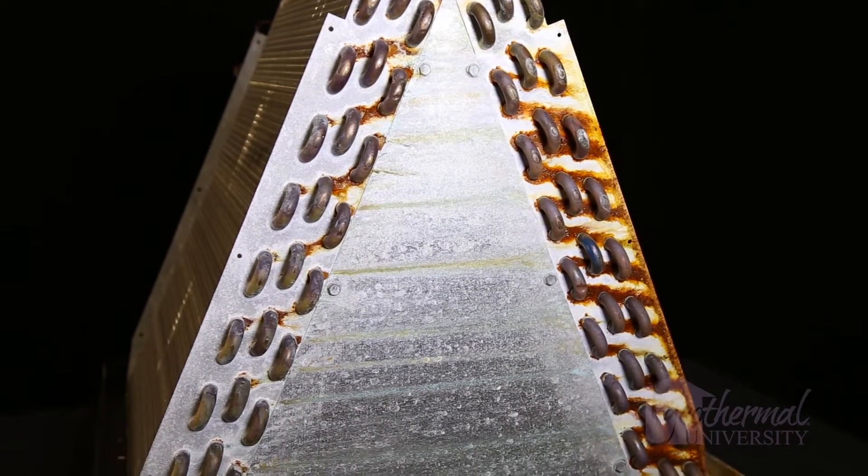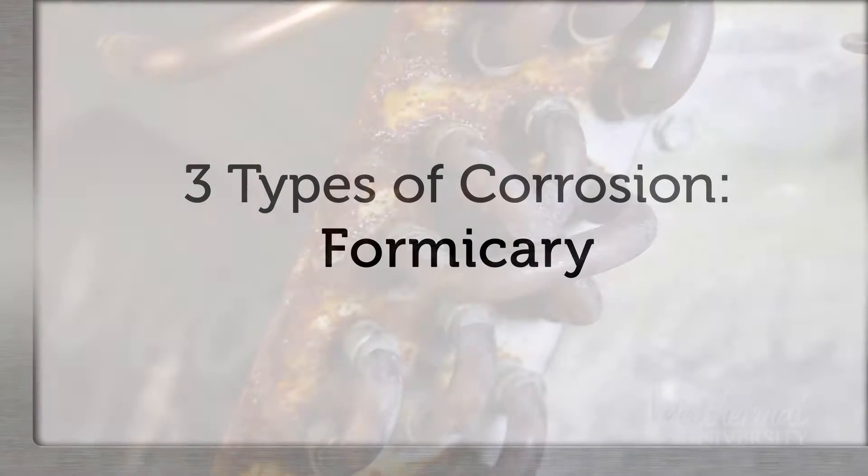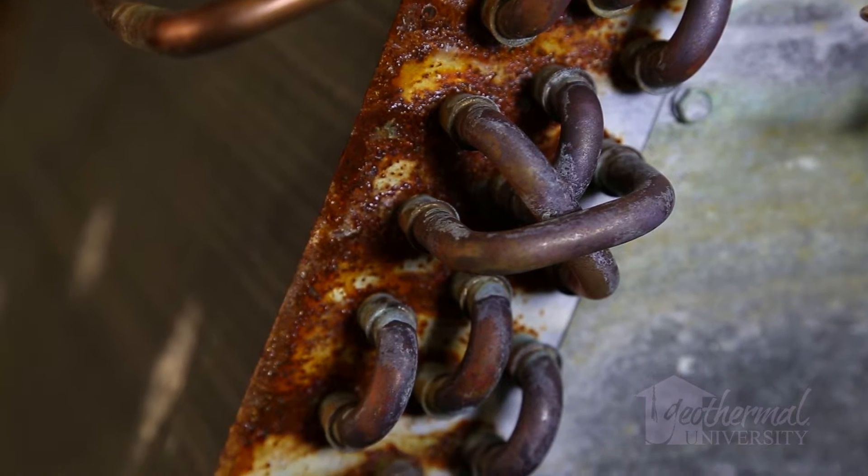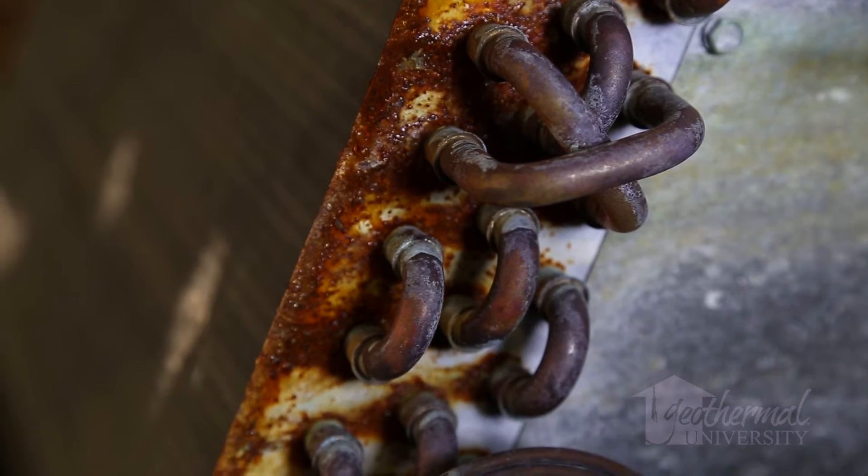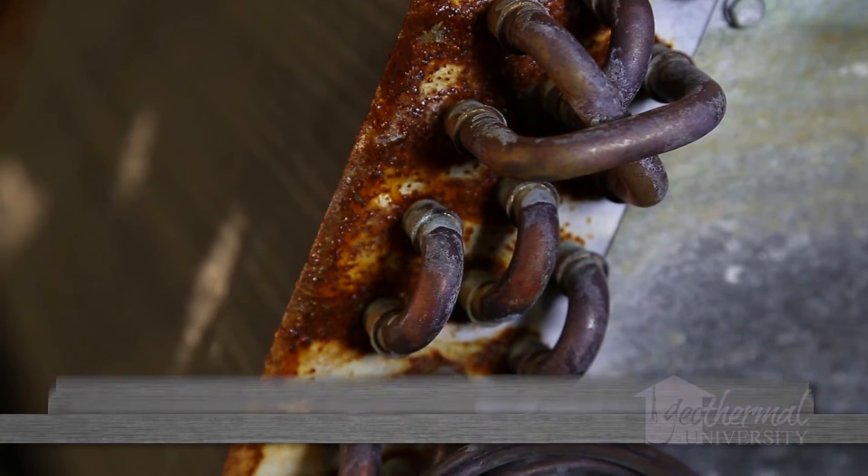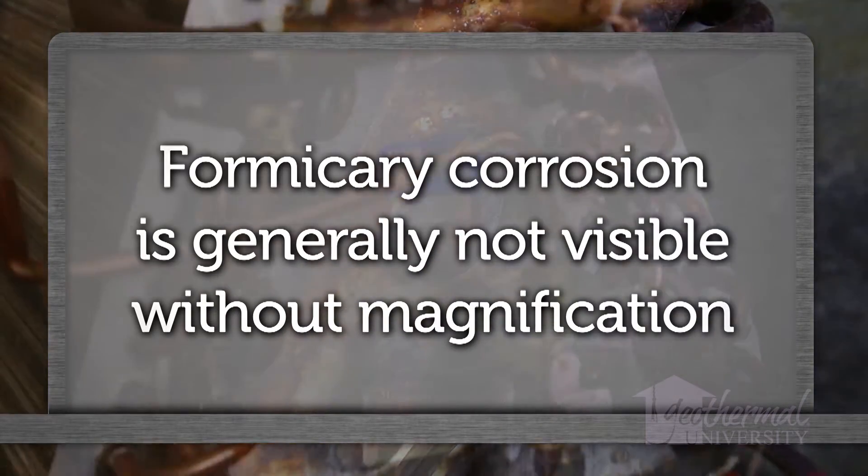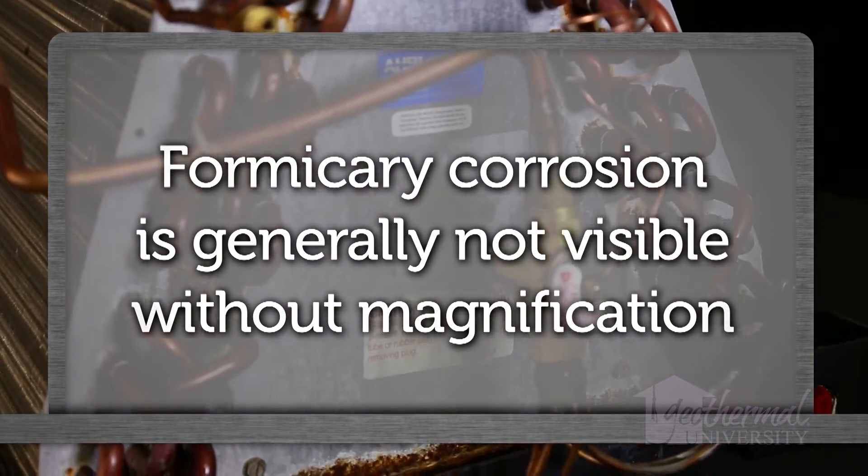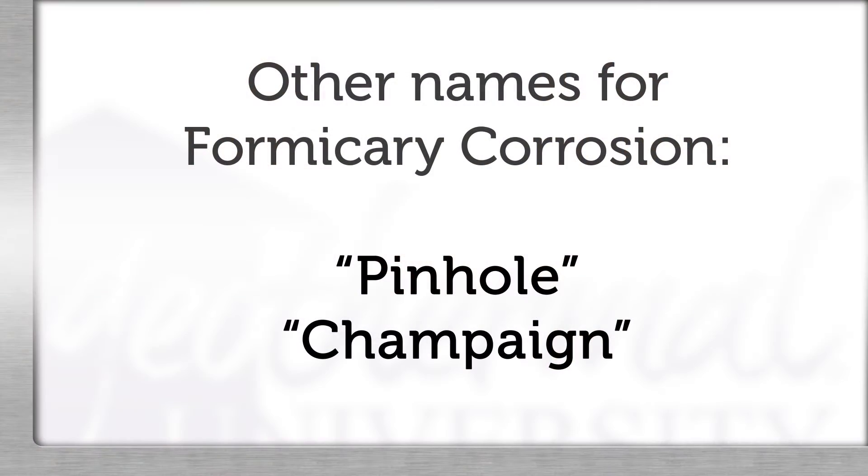Electrolytes are drawn to a crevice through capillary action. Formicary corrosion only occurs in copper-based alloys and HVAC coils made of copper. If you see corrosion it is probably not formicary corrosion because it is not generally visible without magnification. Other nicknames for formicary corrosion are pinhole or champagne leaks due to the micro size of the actual holes in the copper.